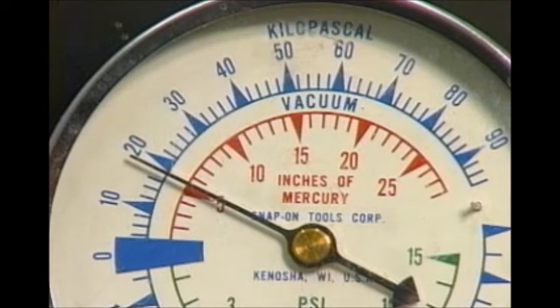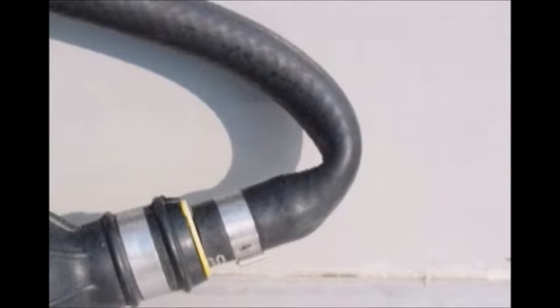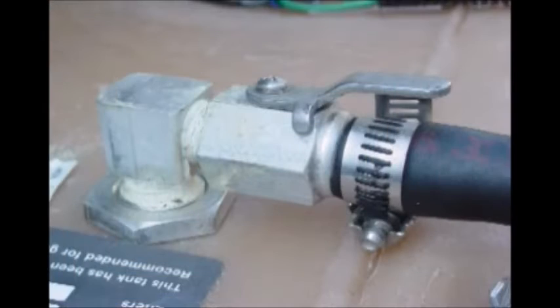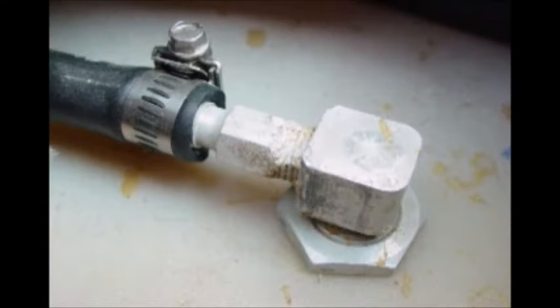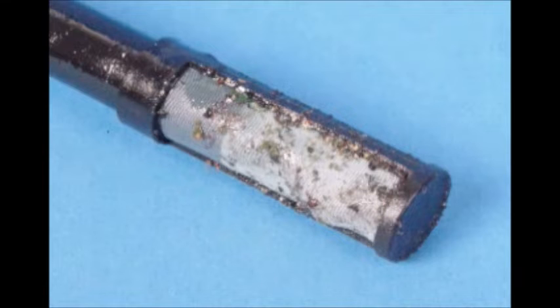A high vacuum reading indicates a fuel restriction. Restrictions can be caused by kinked hoses, fittings that are too small, stuck or poor quality anti-siphon valves, or debris on the fuel tank pickup's strainer screen.